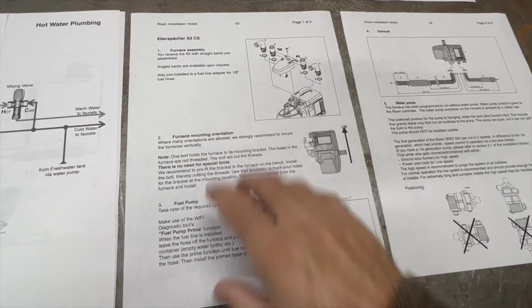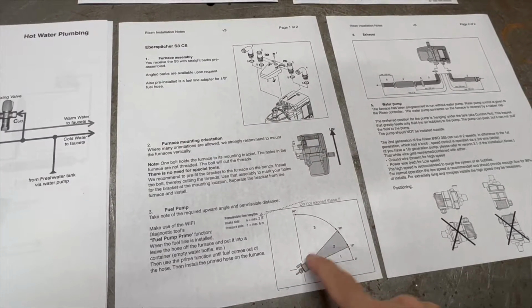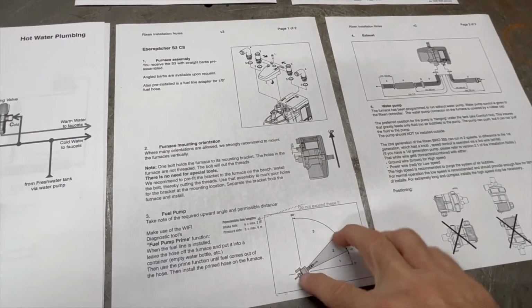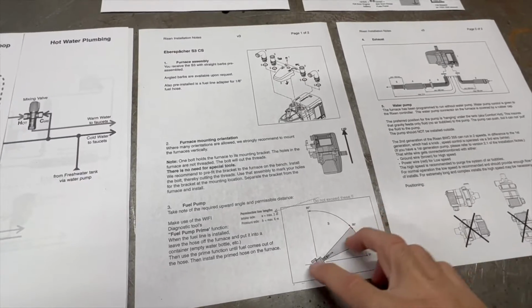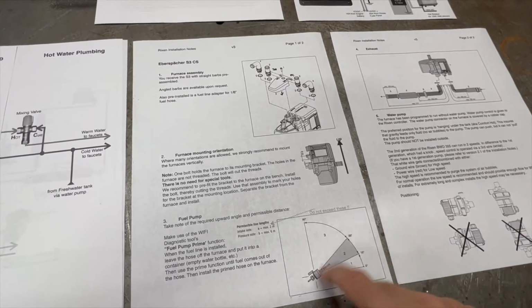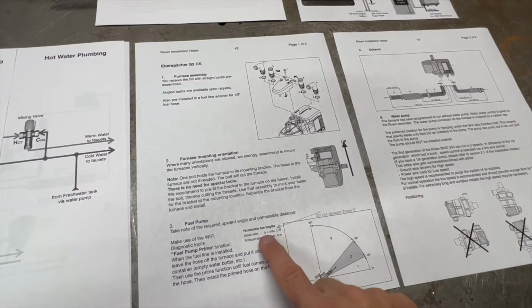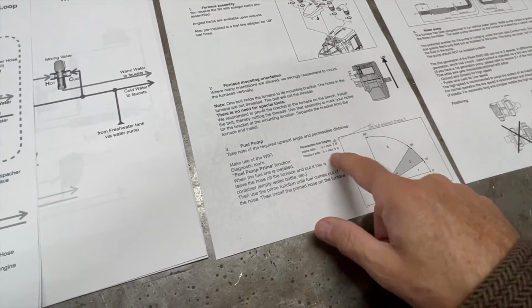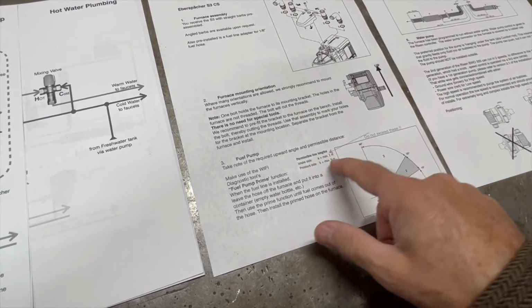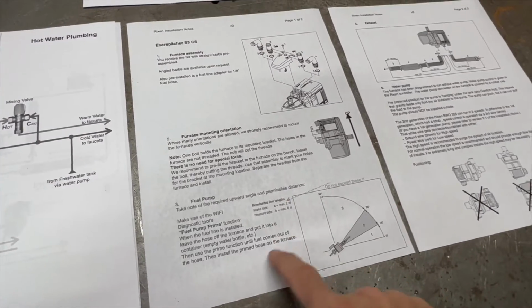This gives us information on the furnace. Now this is the fuel pump for the furnace, and it says you have to have it tipped between 15 and 35 degrees in this direction for the fuel pump to work properly. You also can't have more than 2 meters of line on the intake side or 6 meters on the pressure side, which is actually pretty far. It should easily fit in there.